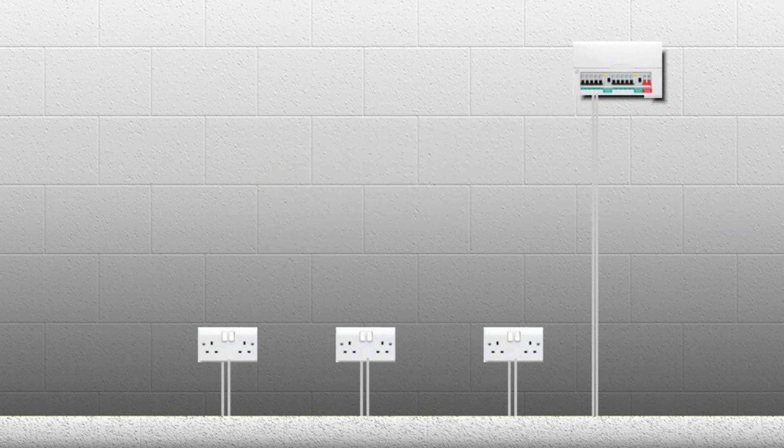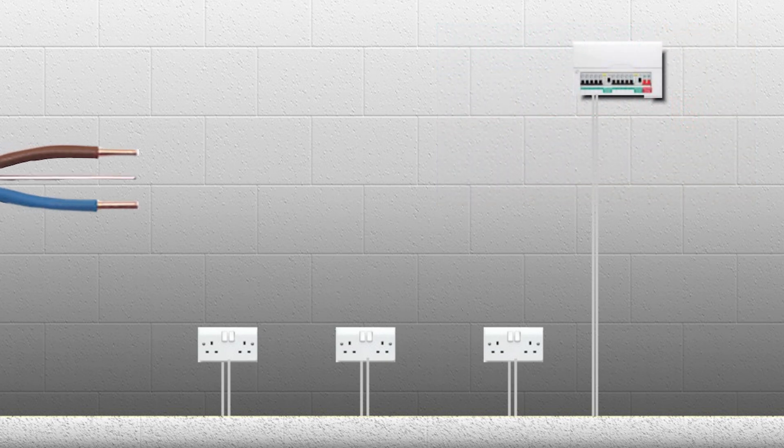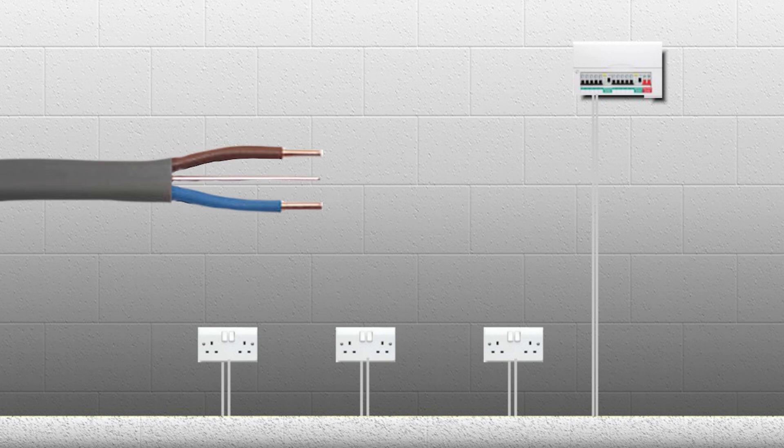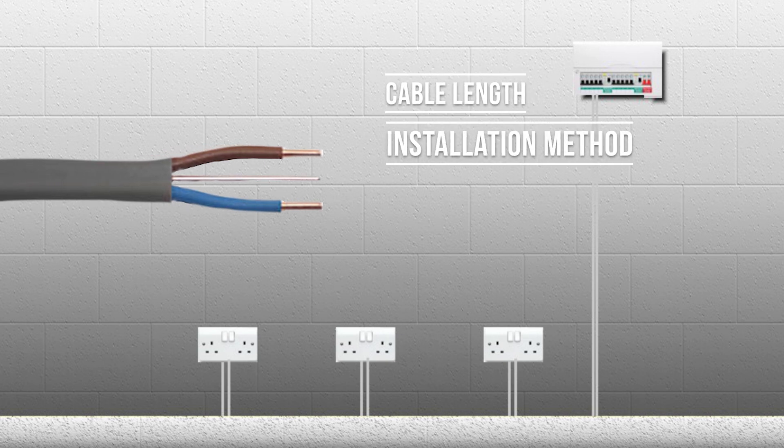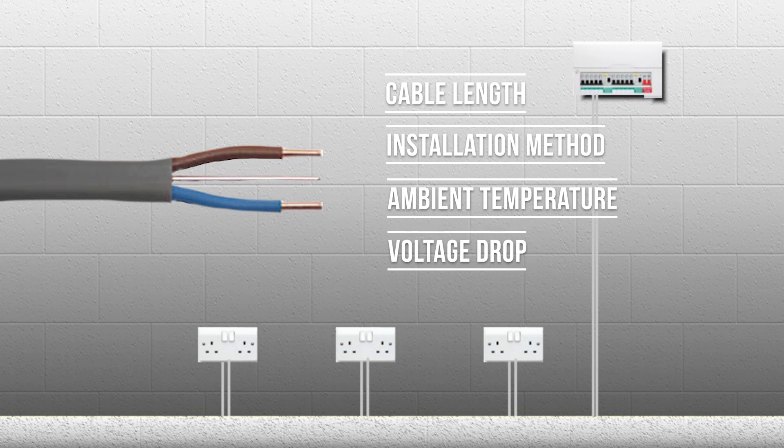Every new circuit has to be designed by calculating the maximum load of the circuit, choosing the right size circuit breaker and calculating the right size of the cable, by taking into account its length, method of installation, ambient temperature, voltage drop and a few other factors and then the whole circuit should be tested.